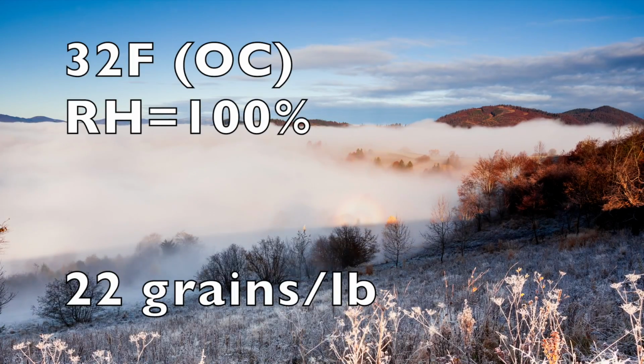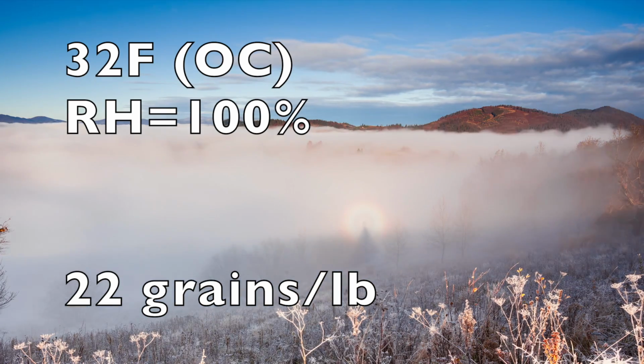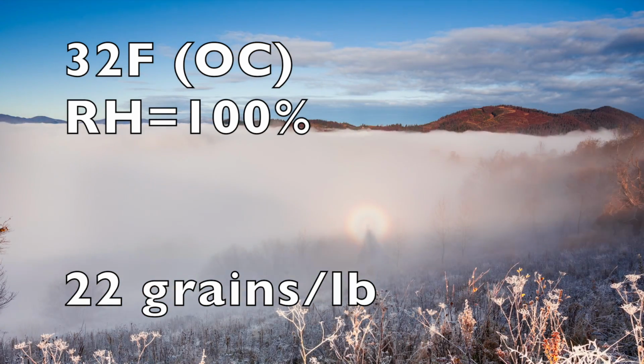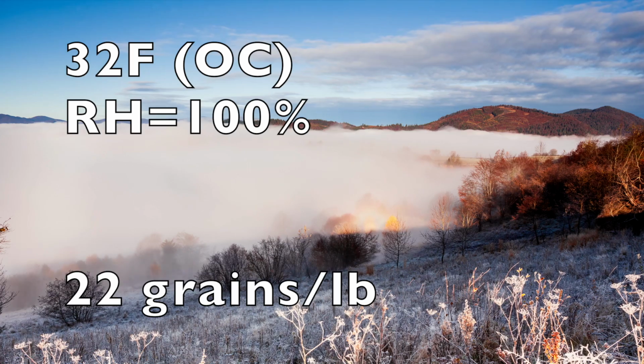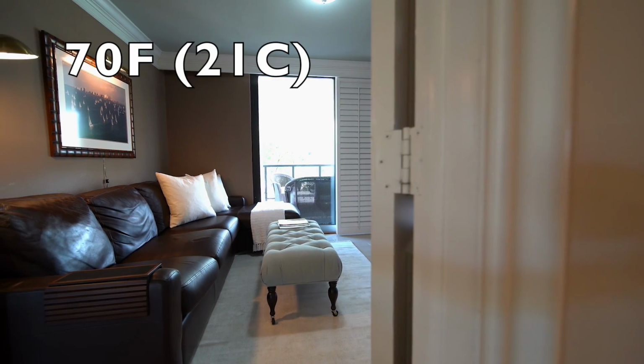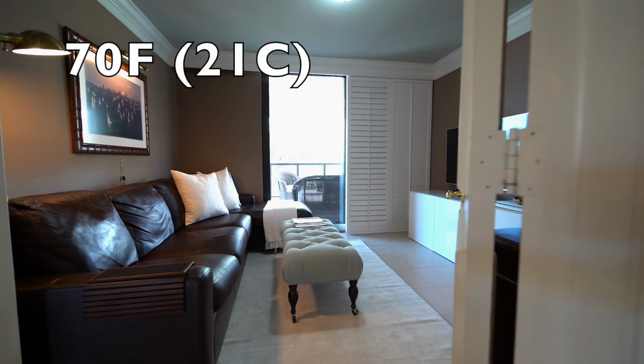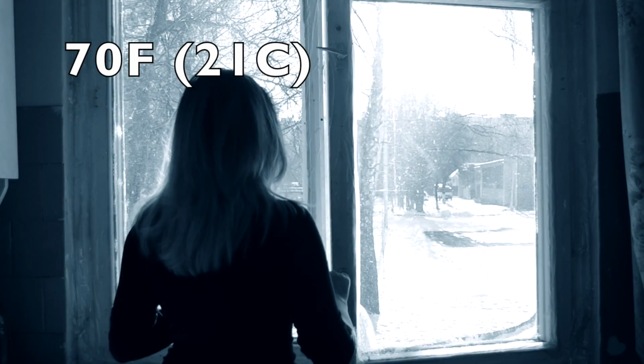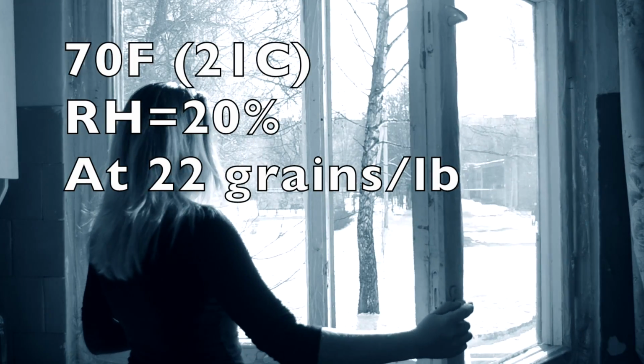To recap, the outdoor air is 32 degrees Fahrenheit with an RH of 100% and 22 grains per pound of water vapor. Let's say the air inside your home is 70 degrees. If that outdoor air leaks into your home, then it warms up to 70 degrees, its RH would then be 20%.